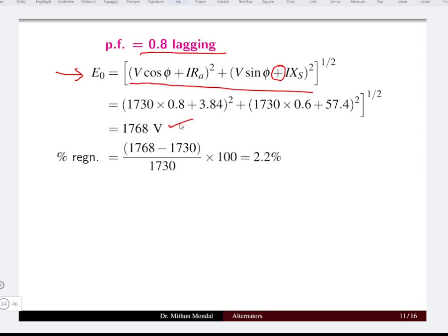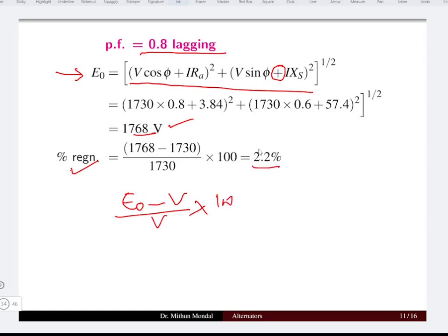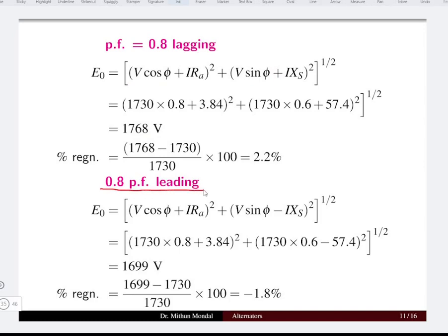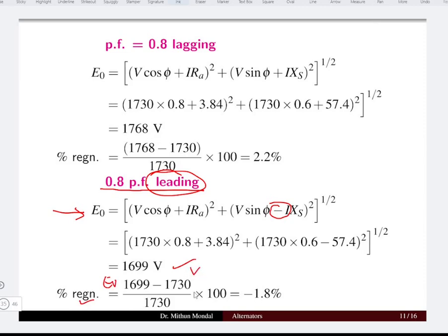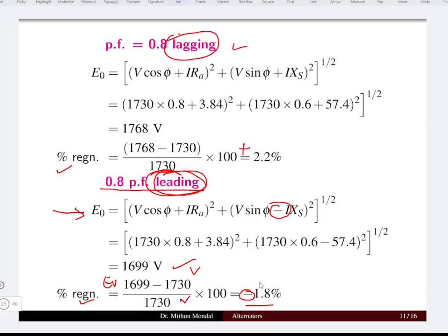The induced EMF under no-load condition is 1768 volt, and percentage regulation equals no-load voltage minus rated voltage, divided by rated voltage times 100, which gives 2.22 percent. For the 0.8 power factor leading condition, a negative sign appears in the equation for induced EMF E0, giving 1699 volt. The regulation under leading condition is -1.8 percent. Voltage regulation is positive for lagging power factor and negative for leading power factor.